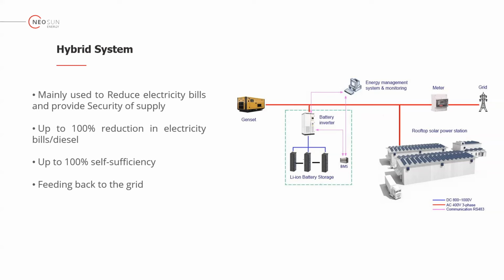There is an option to integrate the generator into this setup. For clients that have only a generator and do not require battery storage, Neosun can put a system in place where your diesel generator synchronizes with your solar PV system and reduces diesel consumption. Since the diesel generator needs to operate at about 30%, we have a control device that keeps your generator running at 30%, while the rest of the power is supplied by solar, giving a reduction of about 70% in diesel consumption.